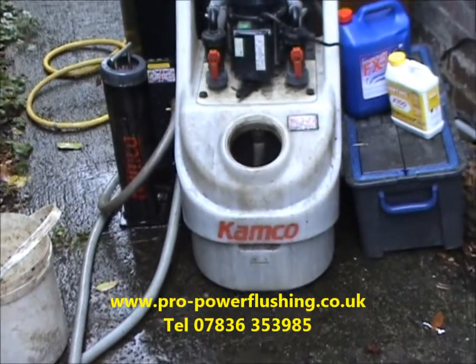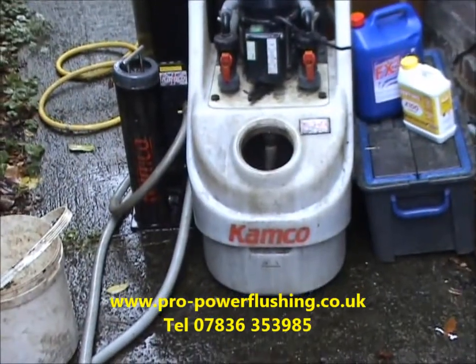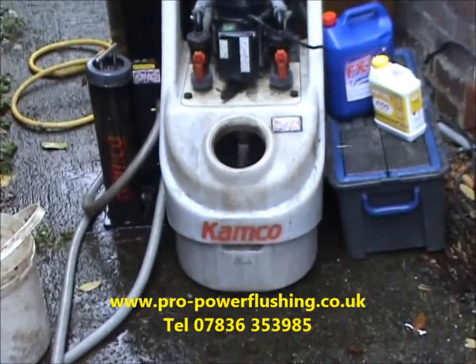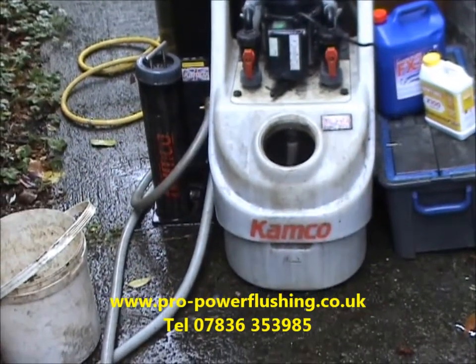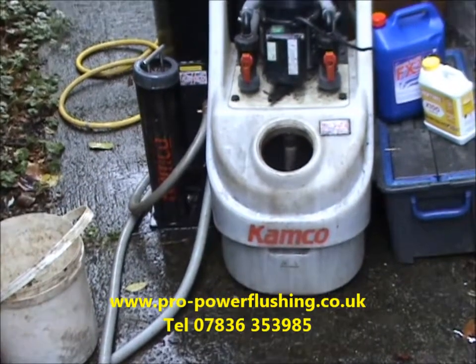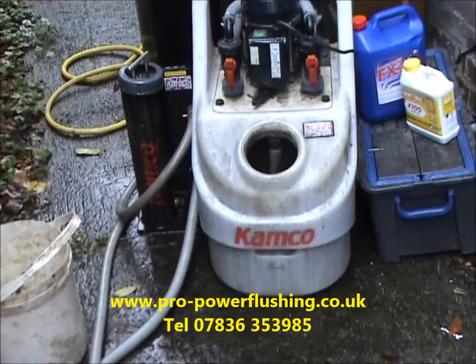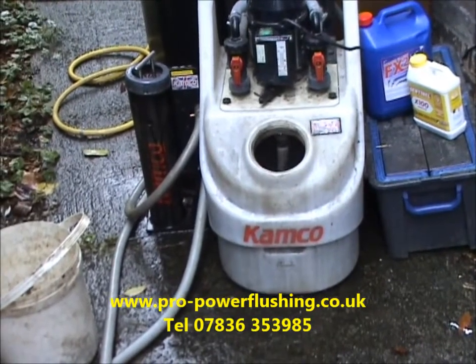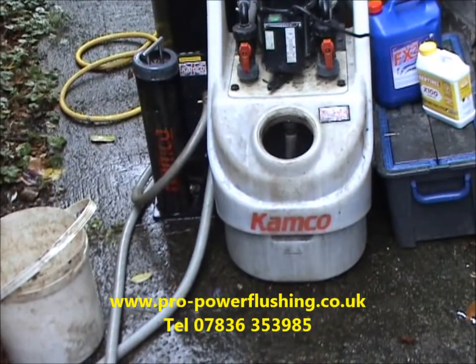We've actually taken the pump off the system so we can get into the big pipes. We don't just pull radiators off. Sometimes we have to do it like that, it just depends where the boiler is. If pipes are buried or hidden and pumps are in very difficult places, we sometimes have to tap in through a radiator. But more often than not, we're looking for the best flow around the system. That's usually the pump housing or the big flow and return pipes going into the boiler.